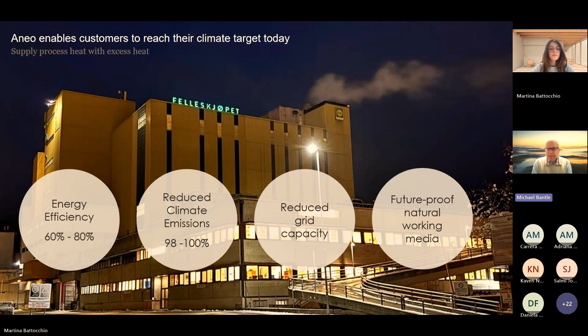Next slide, please. Yes. So this heat pump installation is reducing the electric grid capacity at this point, close to the city center in Trondheim, by 1.2 megawatt electric, basically by utilizing the same amount of thermal energy from the existing exhaust. And in the current installation, with around 5,000 operational hours per year, we supply around 7.5 gigawatt hours of process steam and energy to the factory.